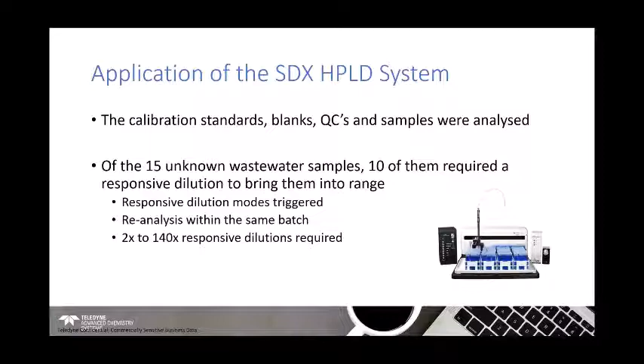washout processes to make sure that after a sample's been diluted and introduced to the ICP optical system, we're now ready for another analysis, and there's no carryover from one sample to another. So we eliminate any kind of issues there, analyte memory effects from known analytes that have that kind of problem, for the sake of argument, something like mercury or iodine. So we can configure the system to the analysis of interest.